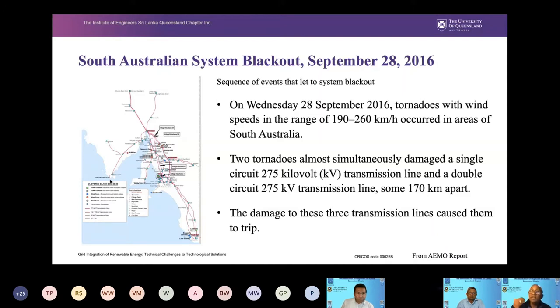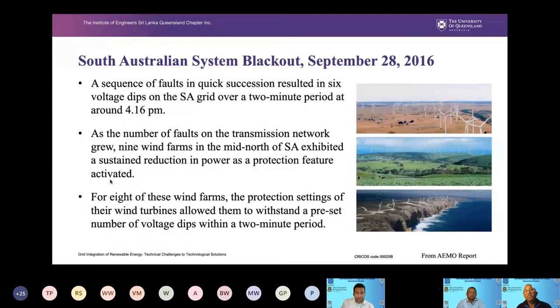When there are faults, these wind turbines, which are relatively new, are vulnerable to them. They react, and then they either reduce power or try to adjust things according to the situation. So this sequence of faults in quick succession, almost 6 voltage dips as a result of these faults, happened over a period of 2 minutes. This happened around 4:16 on September 28th. A number of faults on the transmission line grew as the tornado continued. Out of the 9 wind farms, mainly located in the mid north of South Australia, as a result of the voltage dips the wind farms showed some reduction in power as a result of the fault activation.